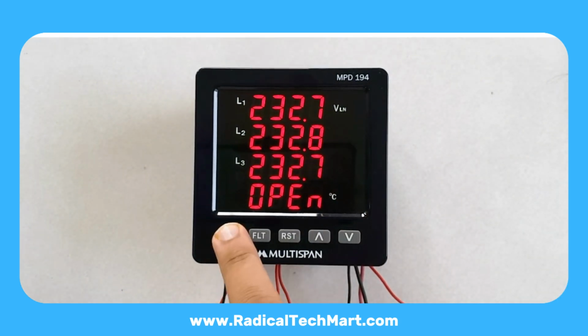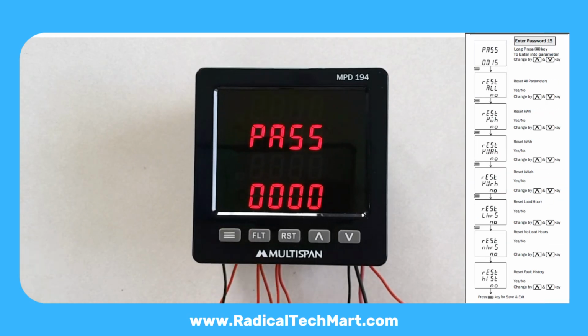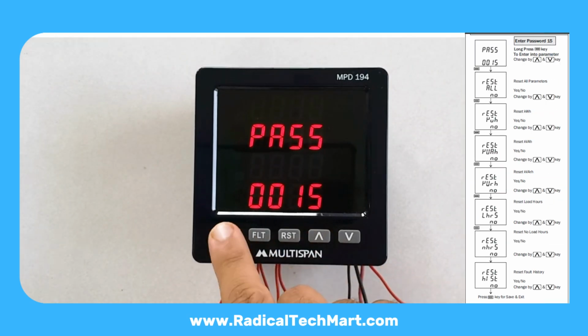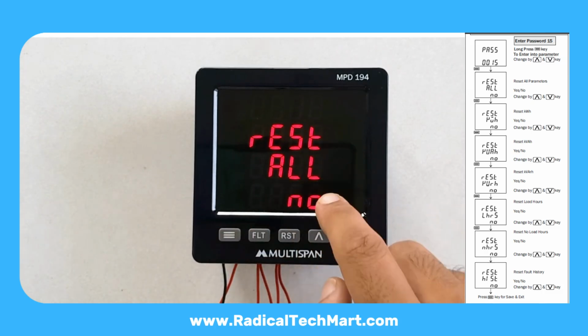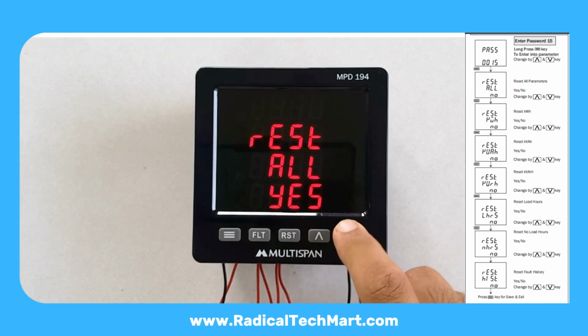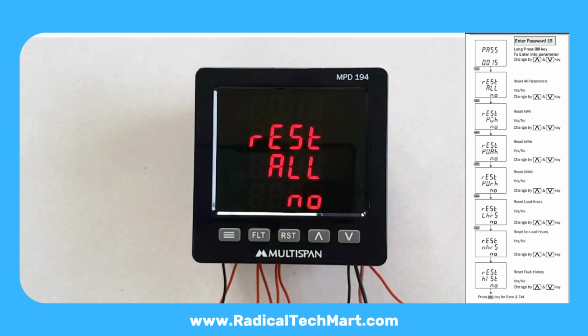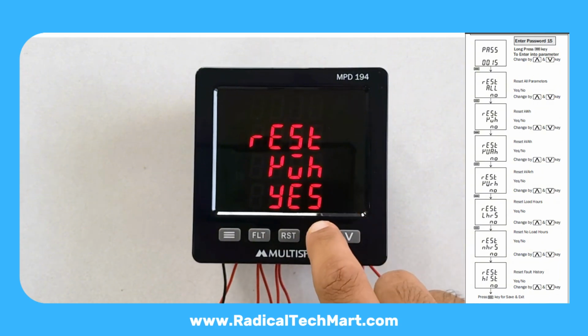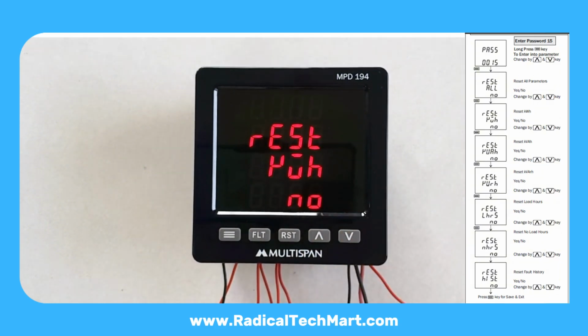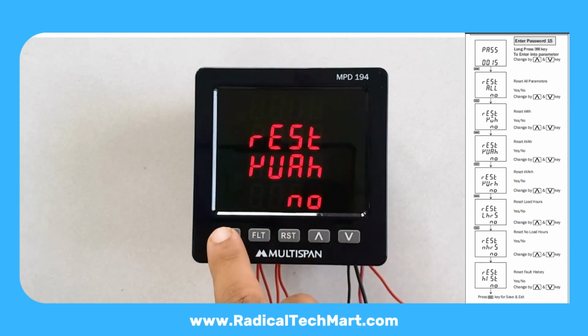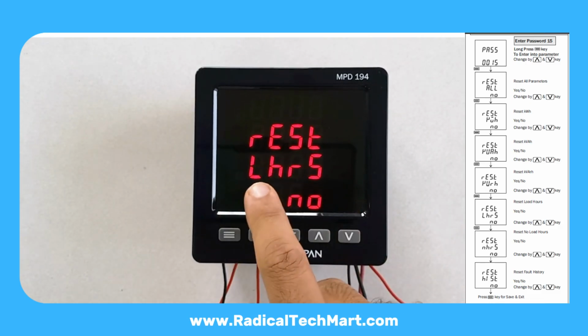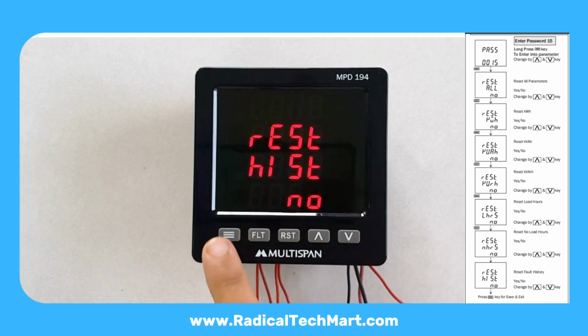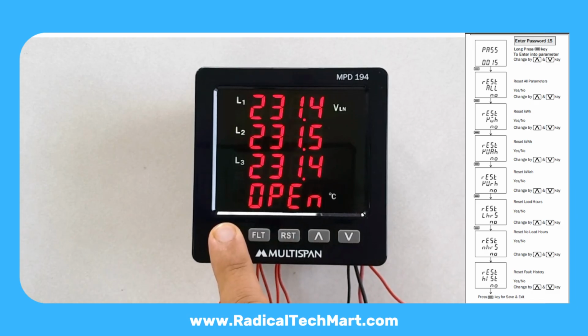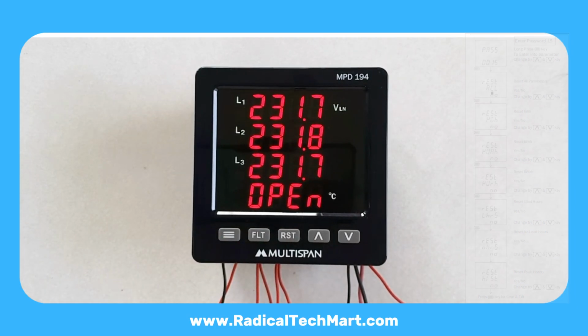To reset energy and logged counters, press and hold Set. Enter password 15. Press Set. First option, reset all. If you select yes and press Set, all energy and logging values will be reset. If you want to reset individually, press Set to move parameter by parameter: kilowatt hour, kilovolt ampere hour, kilovolt ampere reactive hours, load hours, no load hours, fault history, etc. For each, choose yes or no and press Set. Then press Set again to exit.